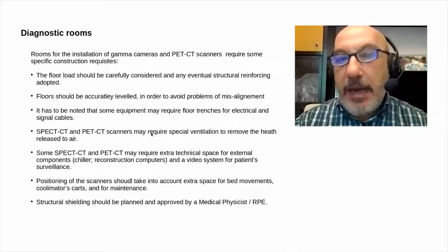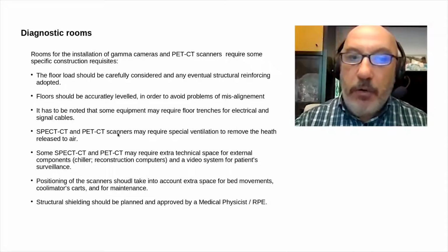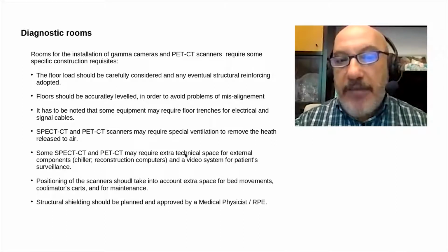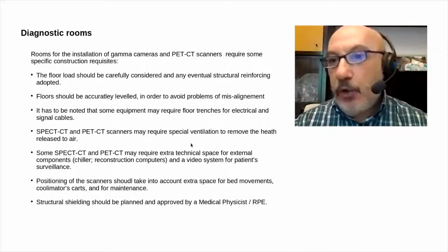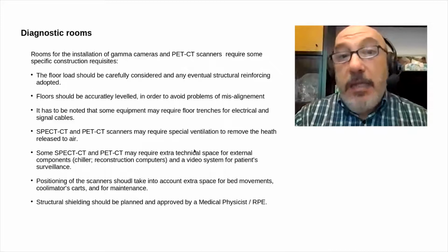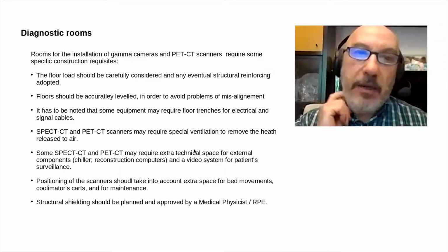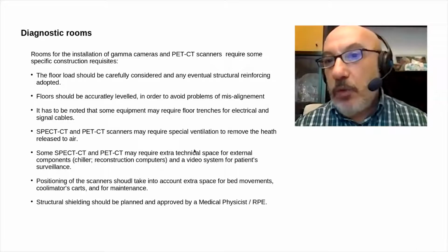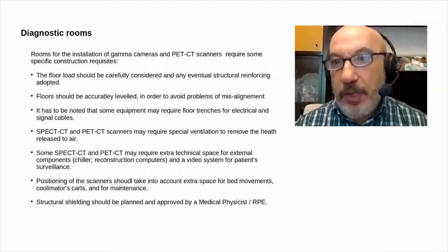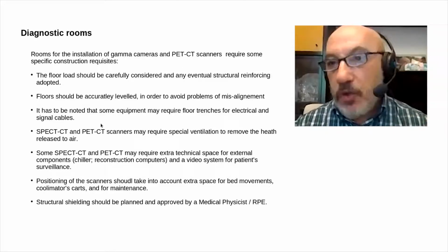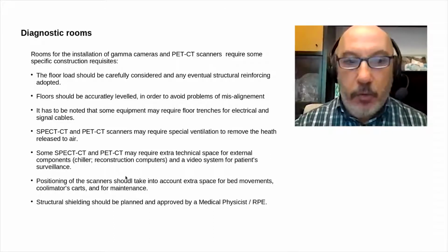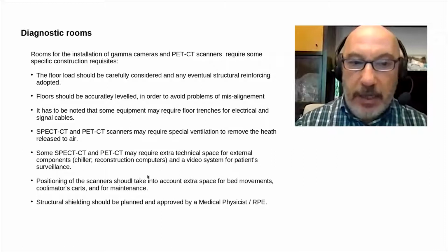Also, SPECT-CT and PET-CT scanners may require special ventilation in order to remove the heat released to air, but some scanners may have an extra chiller that has to be properly hosted in a small dedicated technical area. They can also be installed within the diagnostic room, but this is not always suggested because these types of devices are noisy, so they may interfere with the normal activity and may disturb the patient, so a properly insulated room adjacent to the scanner room is the suggested solution.